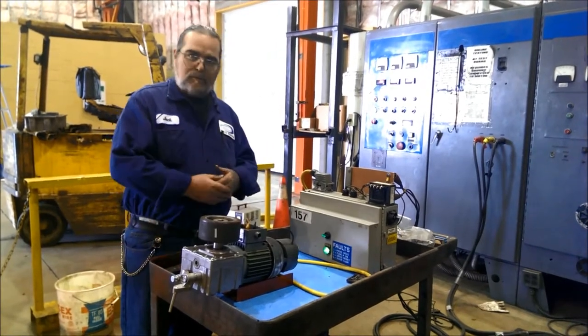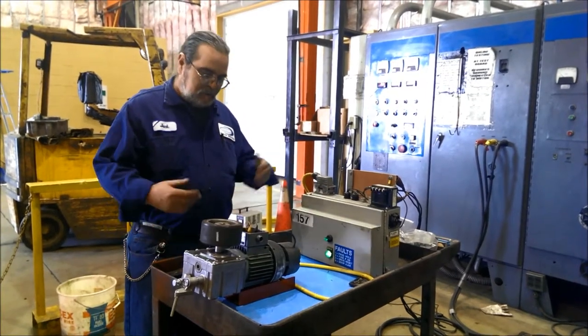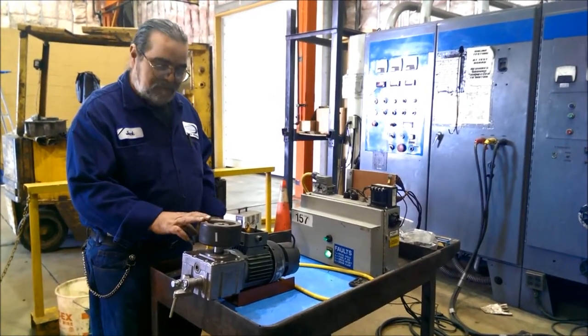We're going to test the motor in the low speed and the high speed, putting 200 volts AC into the motor, which is what they require at GM. We're looking for an optimum output of 100 RPMs in the high speed and 15 RPMs in the low speed.